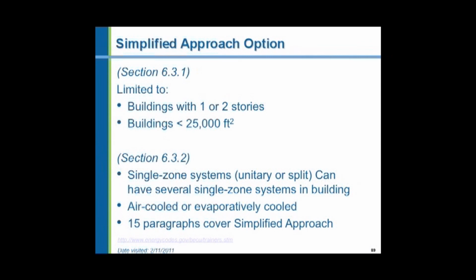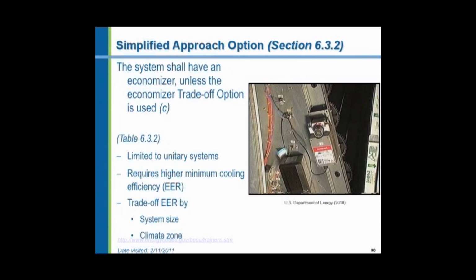First of all, we're looking at a single zone heating and air conditioning system. Now, it doesn't say how many zones you can have in these buildings. There's no requirement, no limitation, but that each zone have its own heating and air conditioning unit. The systems have to be air-cooled or evaporatively cooled, have to have an economizer unless you increase the efficiency of the air conditioning system so that you can get away without an economizer. Economizers are limited to unitary systems, and it can be an EER trade-off according to system size or climate zone. Now there's some little requirements in there, but they're very easy.